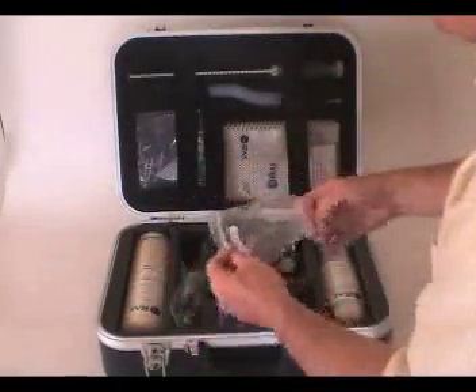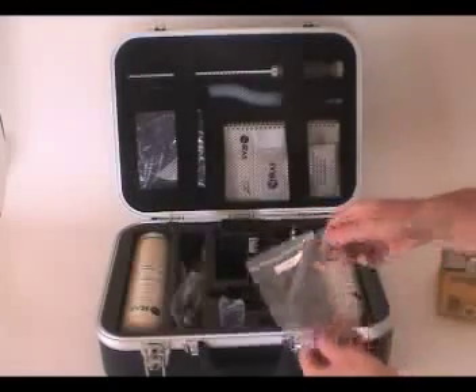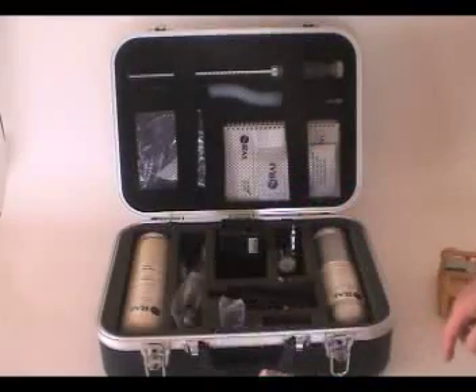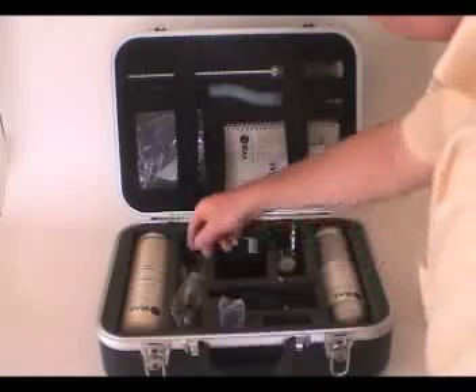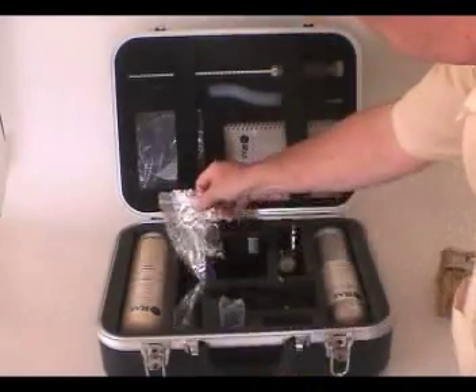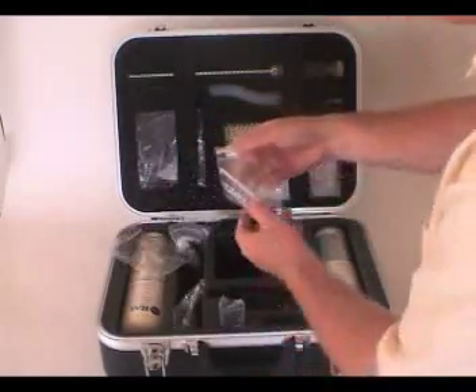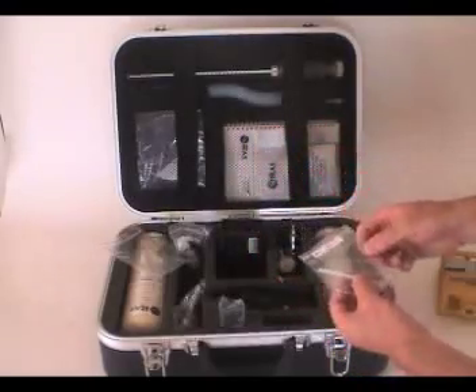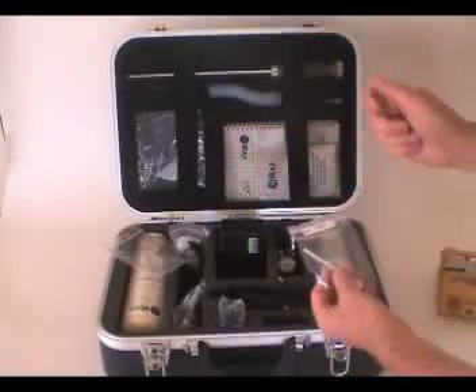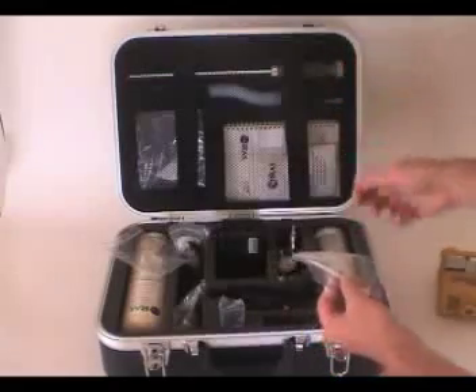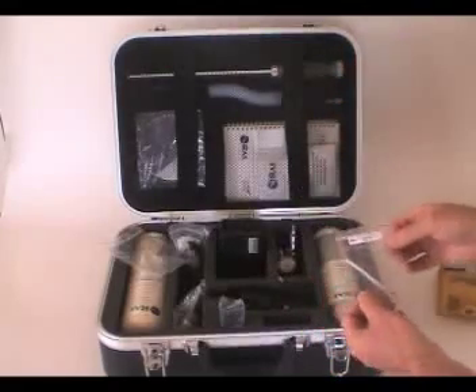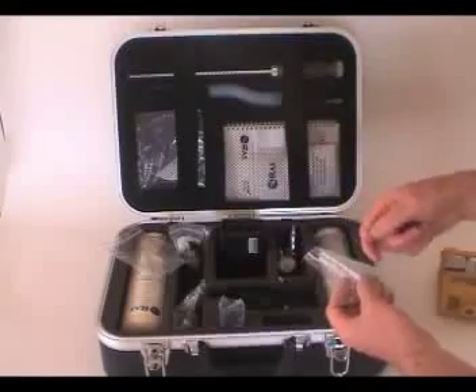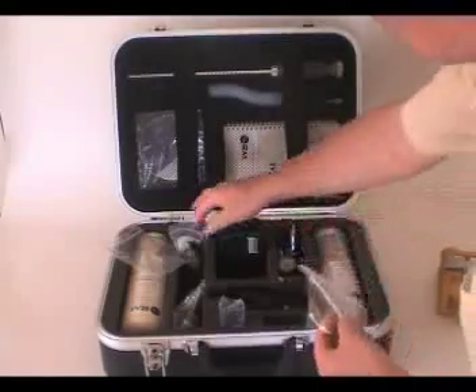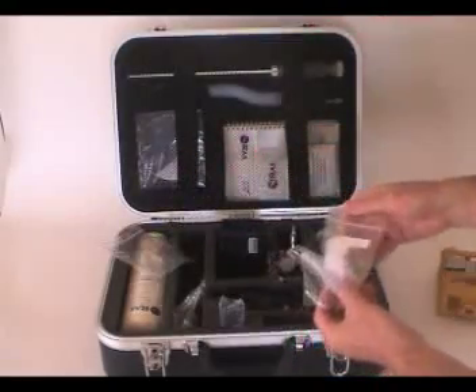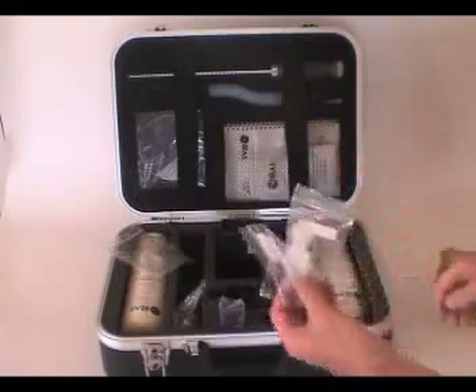We have the calibration adapter, which allows us to hook up to our calibration gases - we'll go through that in a later video where we'll actually calibrate the unit. It's very simple. There's also an inlet probe - a hard probe on a coiled adapter - but if you just want to use the unit directly, you can hook on a filter like this one in-line to keep the schmutz out.